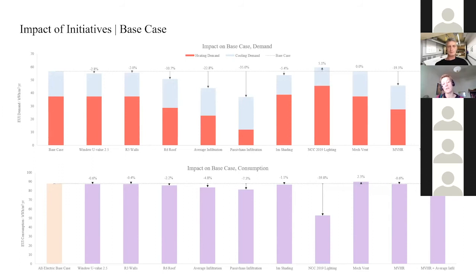At the far right end of the bar chart, if we incorporate mechanical ventilation with heat recovery and improve the infiltration rate, we end up reducing the heating and cooling demand by about 60%. There are also huge benefits for thermal comfort and indoor environment quality, since you're removing gaps, cracks, and leaks within the facade while still providing enough fresh air for a high quality space.